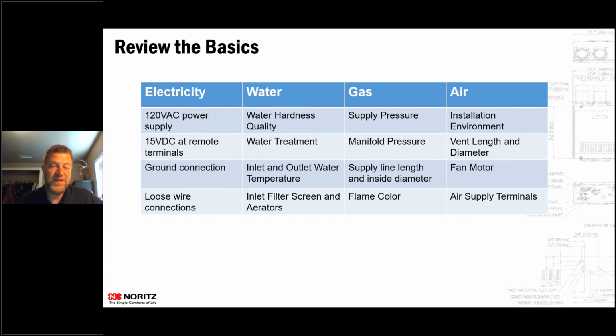Clean the inlet filter that goes into the unit. Every single one of these units, ours, everybody else's, has an inlet water filter going into it. So that's something you want to pull out and clean out, which is very easy. You can just take a little brush, clean it out, run it under water, and it cleans it out. The gas supply, you always want to make sure that the supply pressure coming in is still good. You can also check the manifold pressures. There's a little port on the manifold to make sure that after it goes through the gas valve, the manifold pressure is good.